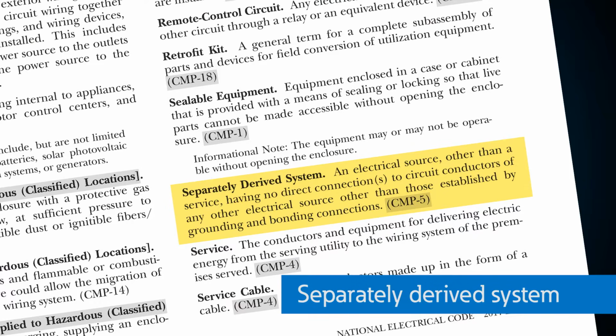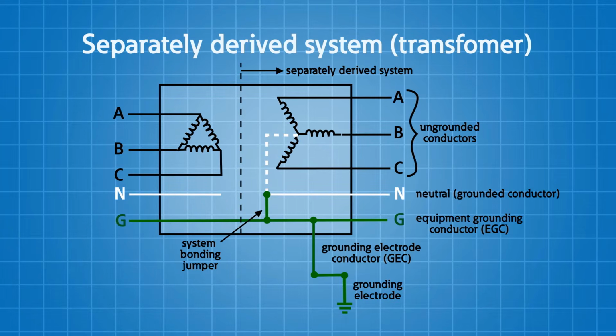Now we're going to move over to transformers for grounding and bonding inside of transformers. When we move into a transformer, we're talking more like a separately derived system. This is your electrical source, other than a service, having no direct connections to circuit conductors of any other electrical source other than those established by grounding and bonding connections. That's your separately derived source. So let's talk about that transformer. A very common transformer you'll have in a power distribution system is your delta-wye grounded transformer. There is an isolation between the primary and the secondary. You're establishing a separately derived system on the secondary of that transformer.